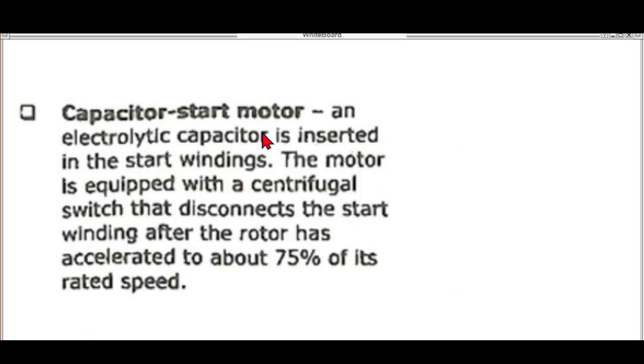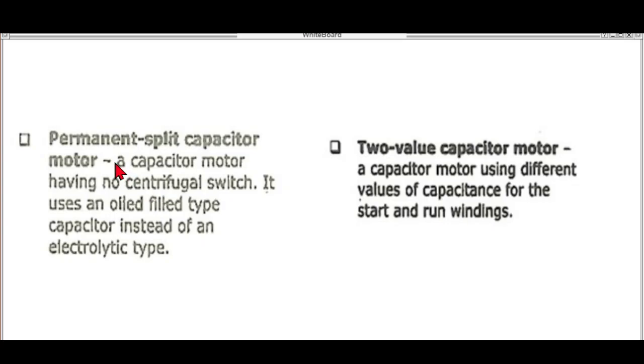So we have the capacitor start induction run motor. So ito yung kaniyang starting winding is may capacitor which will disconnect, no, the switch at about 75% of the rated speed ng ating motor. Ibig sabihin nun, pag lumampas yung speed niya ng 75%, yung mismong motor will now be running using its running winding. Then permanent split motor is a capacitor motor that has no centrifugal switch. So it uses an oil immersion field type capacitor instead of an electrolytic type. Then two value capacitor motor, a capacitor using different values of capacitance for the start and run windings, no?